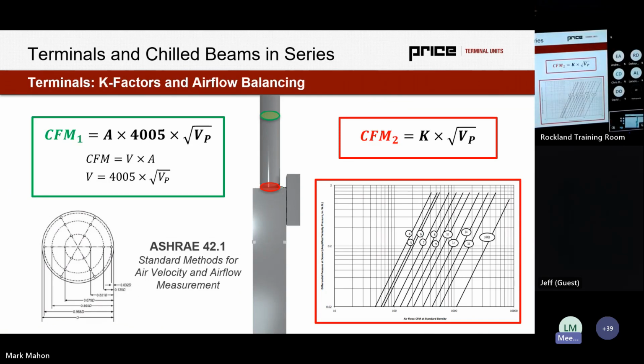So when we look at airflow balancing for a terminal, we're really trying to look at two different points of airflow measurement and bring them together. We're trying to have a pitot traverse upstream in the ductwork, which is based off of velocity pressure measurements that we're going to take through the ductwork. We're going to look at the K-factor crossflow sensor measurement, and we're going to adjust this K-factor to essentially rectify any differences we have between these two equations.